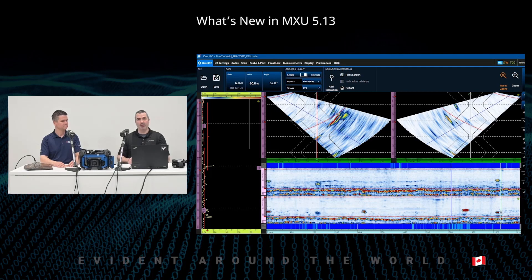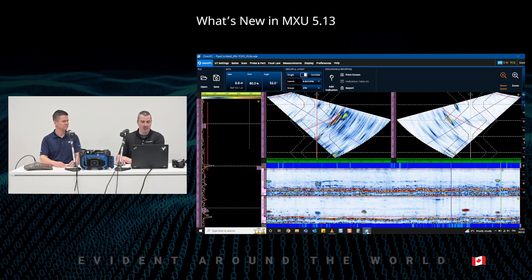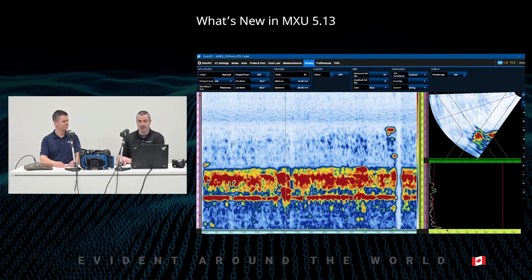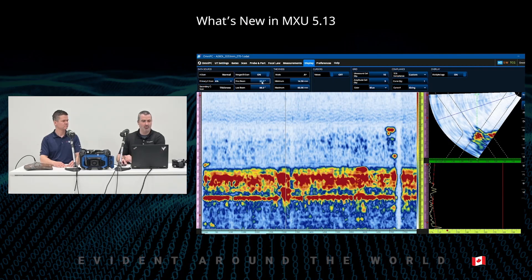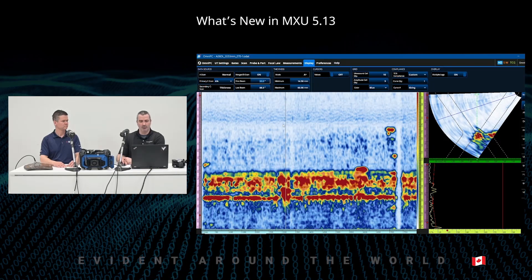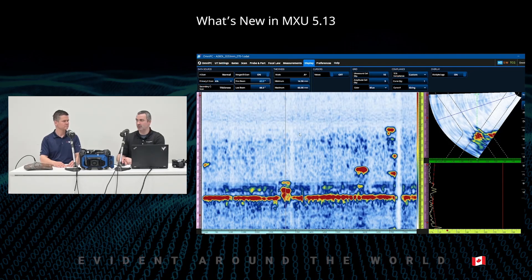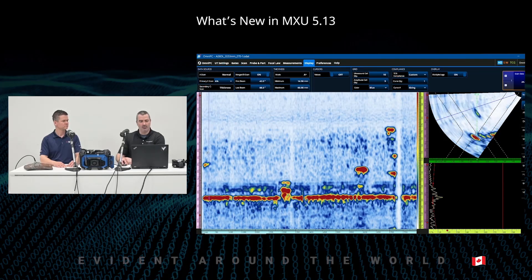This works with linear probes as we see here, but also with dual matrix and dual linear array probes. A typical configuration goes from root to cap in a single scan using longitudinal waves. There's quite a bit of noise from the ID — whether it's rough surface or cladding. With the merged B-scan, we can eliminate that by cutting off the first few angles, going from 30 degrees and moving up. We still have all of our indications and defects without them being overshadowed by the geometry.